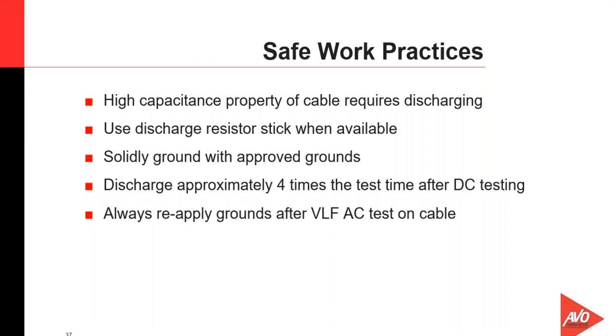If we have been DC testing, the recommendation is to ground the cable for a minimum of 4 times the time that you actually had the test set connected to it. If you're performing VLF AC testing, then you can just reapply grounds after the VLF test set has been turned off, and the condition then can be put in electrical safe work condition.